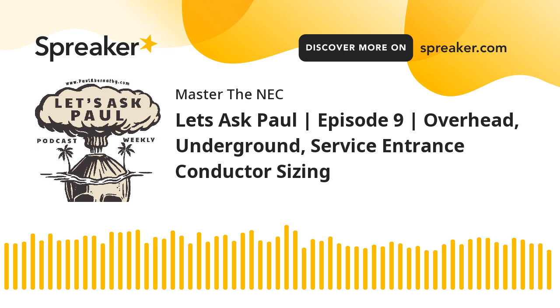Now, chances are the calculated loads are going to be larger than that anyway, but that just gives you some direction. Now, when it comes to the grounded conductor, because we're going to size those ungrounded hots based on part 3 or part 4 of Article 220, we're also going to size the grounded conductor as part of part 3, not part 4. Part 3, because 220.61 appears in part 3, which deals with the grounded neutral conductor sizing. It's not over in part 4. It's in part 3.